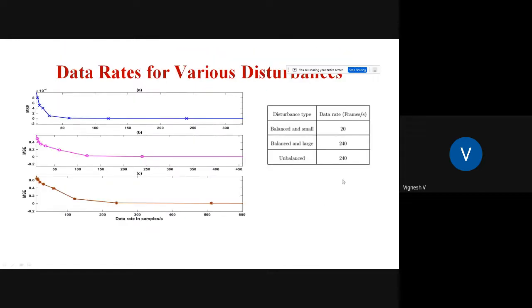Okay. So this shows that for balanced and small disturbances, a data rate of 20 frames per second, 20 phasors per second, would be good enough to get a very reasonable accuracy. And for balanced and large disturbances, we need 240 frames per second to achieve the same accuracy. So in case you reduce the data rate, your accuracy would go low. For unbalanced disturbances, we still need 240 frames per second, because you have a 120 hertz phenomenon coming out because of the negative sequence that comes with the unbalanced disturbance. So the disturbance type also dictates the data rate that you should get from the PMU. Next slide.